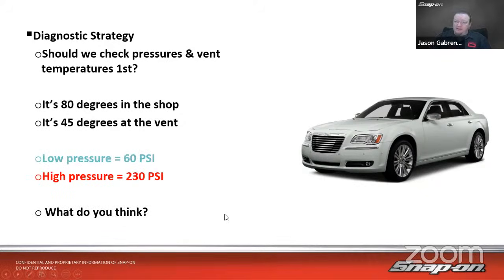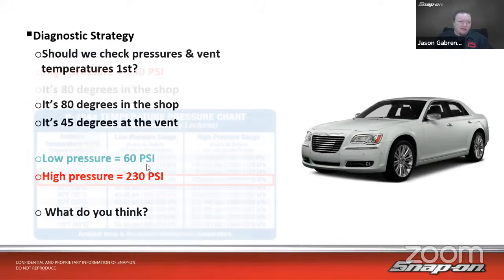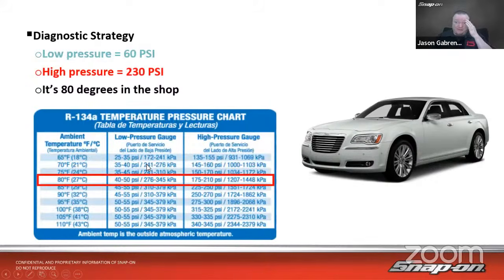So low pressure is 60 psi and high pressure is 230 psi, is what we're seeing there. So 80 to 45, that's a 35-degree drop. That's close. It's on the edge. And then low pressure and high pressure, well, I don't know what the pressure is supposed to be. Usually it's pretty close to ambient, right? So let's look at the chart.